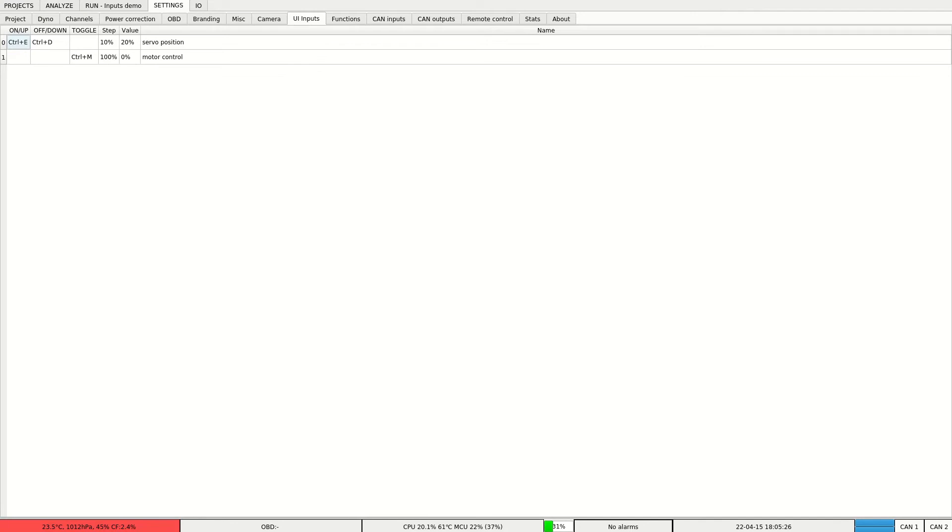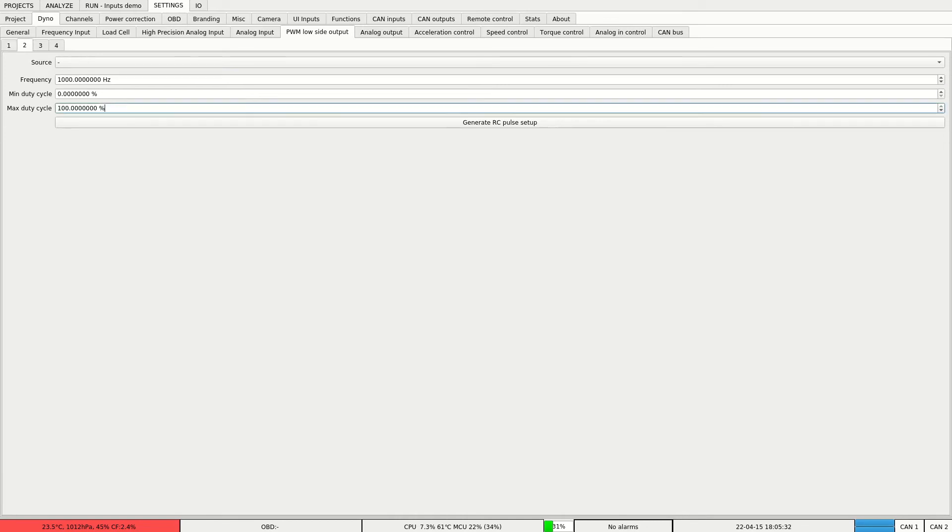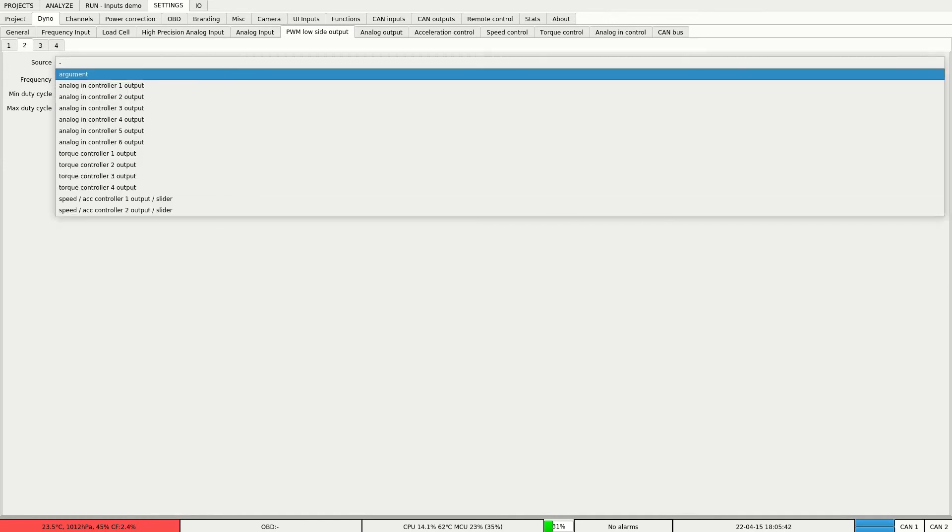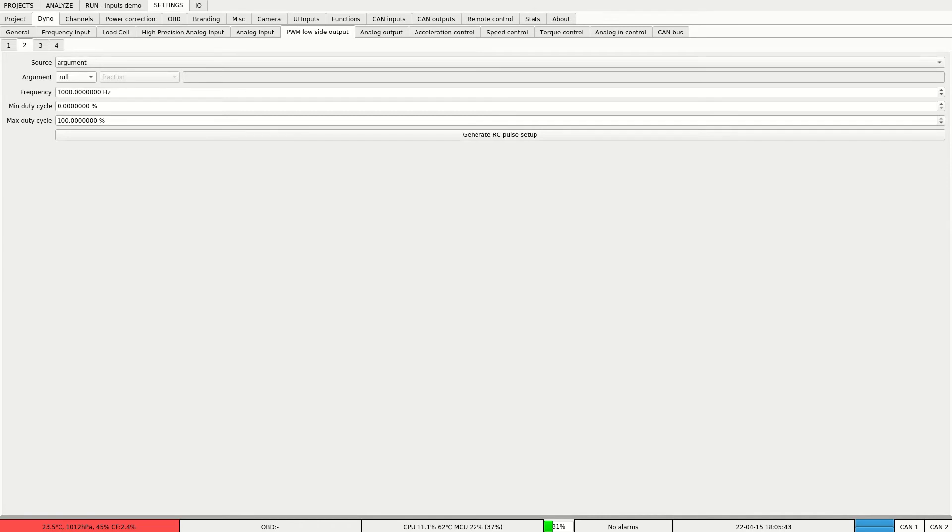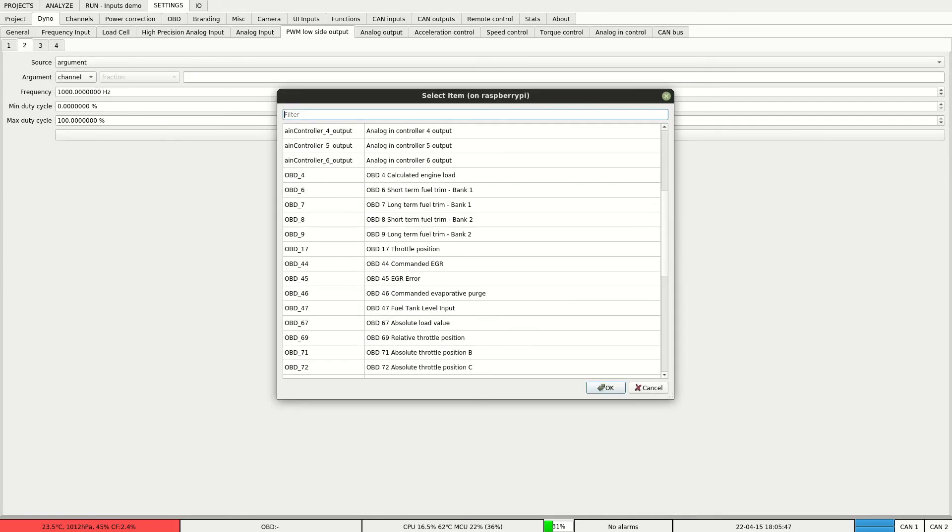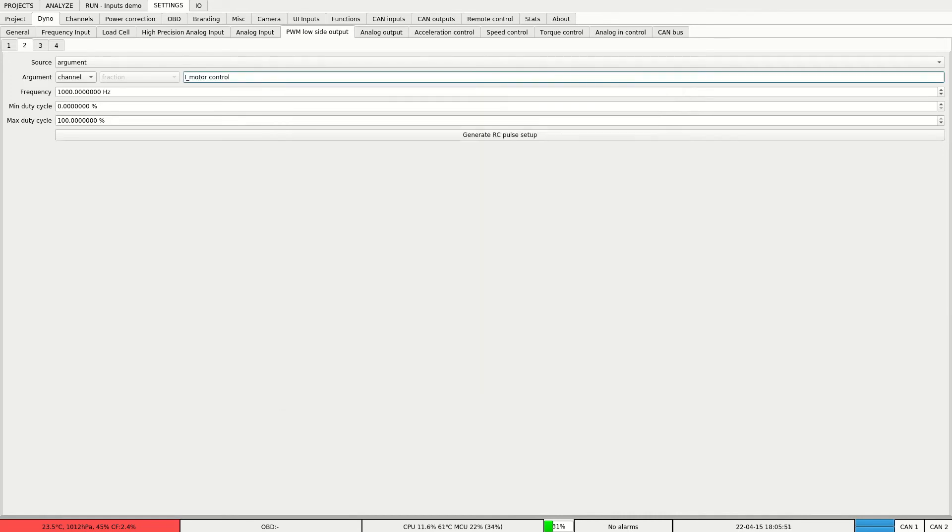Let's go to output setup. It's on the second output. We leave the configuration as it is because it's DC motor. We set the source again to argument to channel and we select our motor control channel.